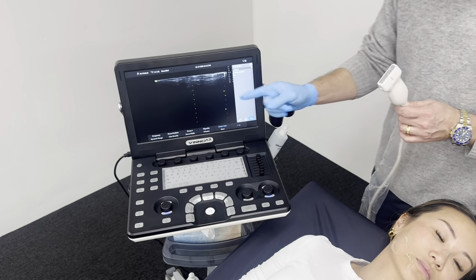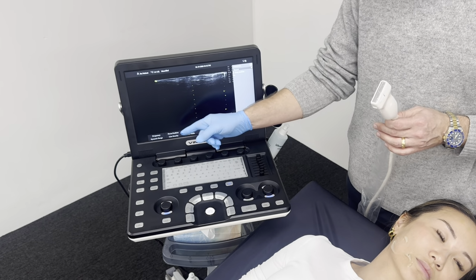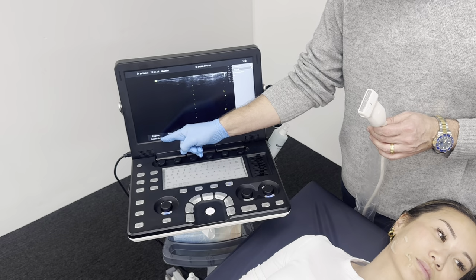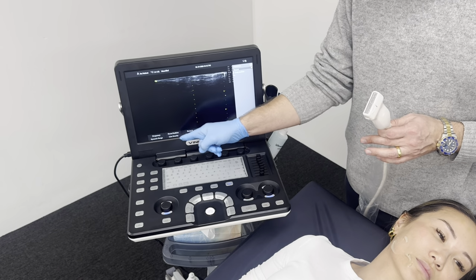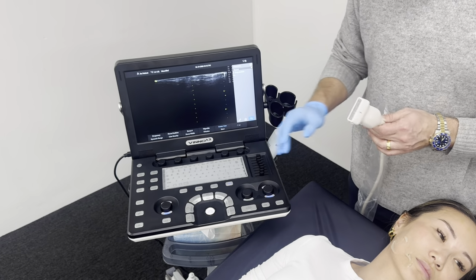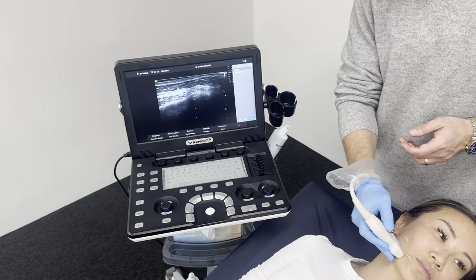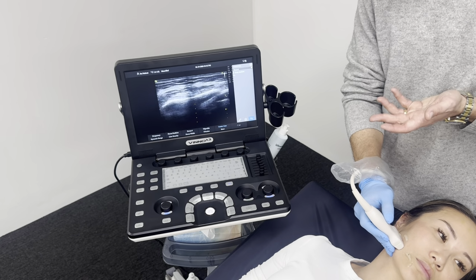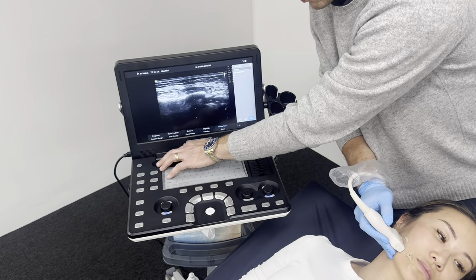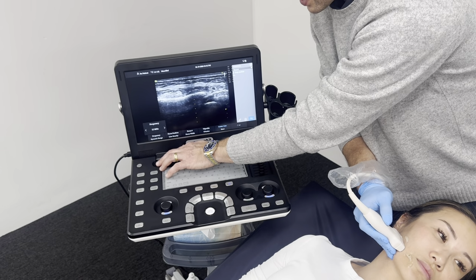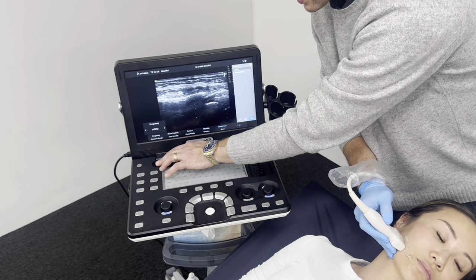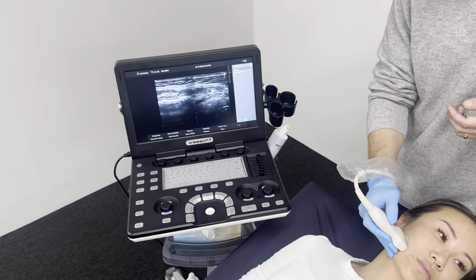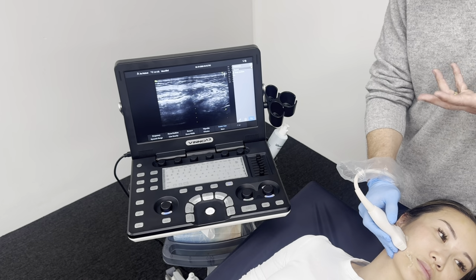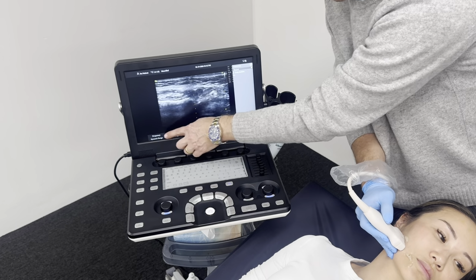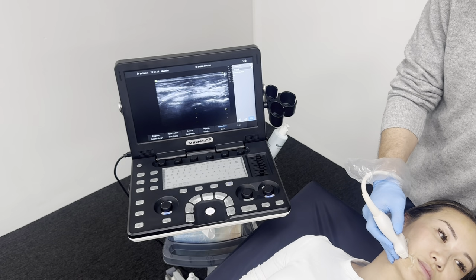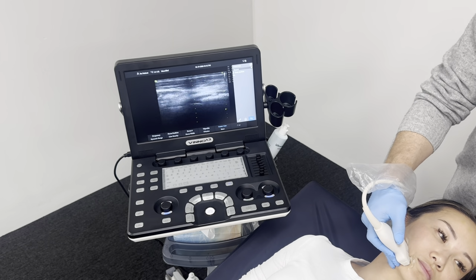The other thing that you can do if you want to adjust the image is change the frequency or the focus position, dynamic range, by using these buttons along the bottom here. If I wanted to increase the frequency, increasing frequency usually gives you better resolution, and it can decrease your penetration a little bit, but it gives you better resolution. You just rotate the knob underneath where it says frequency. Now I'm at 16 megahertz and we can see the image nice and clear.